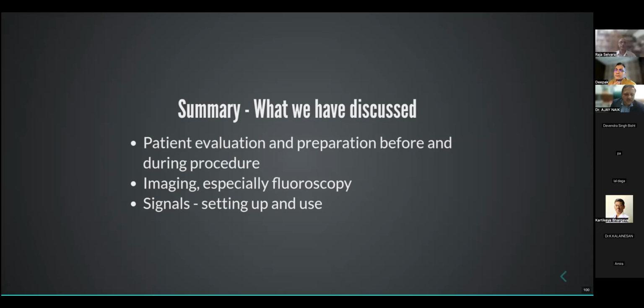I think, like you said, if it's specifically happening during ablation, that is one thing to see, because like I said there, you have to have these signals balanced, and when you open it for pacing, that doesn't happen. So you have to turn off pacing. Also check your ablation cables, ablation catheter. Sometimes it might be a problem in the cable. Also, you have to change your connector and see.